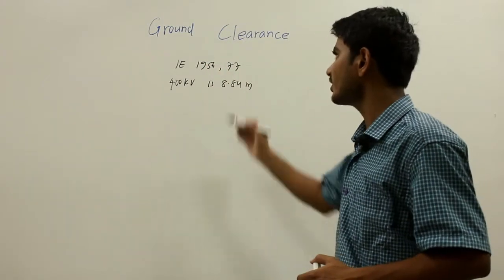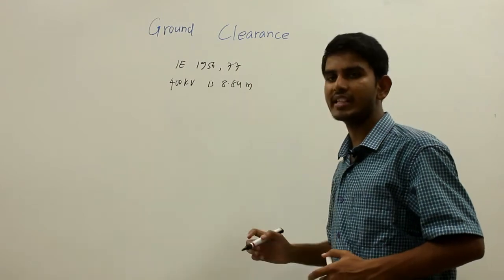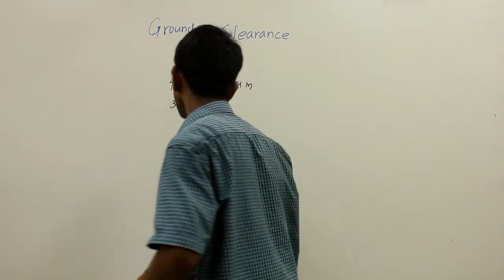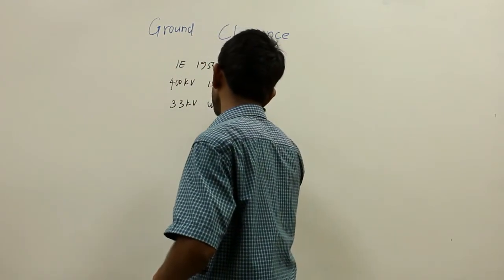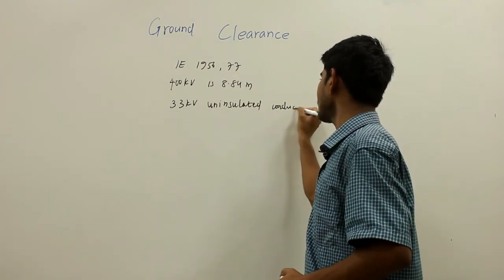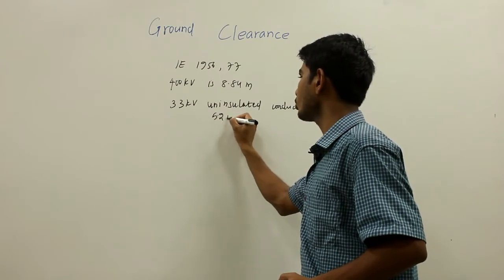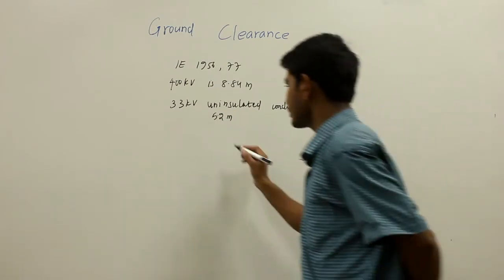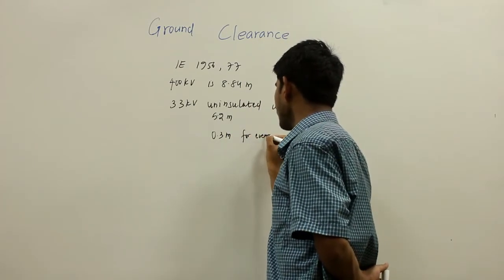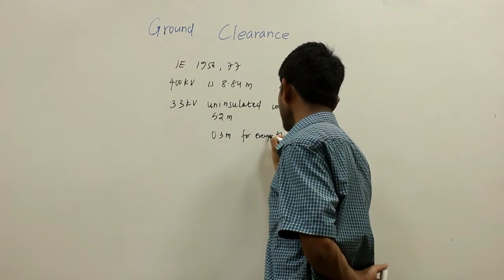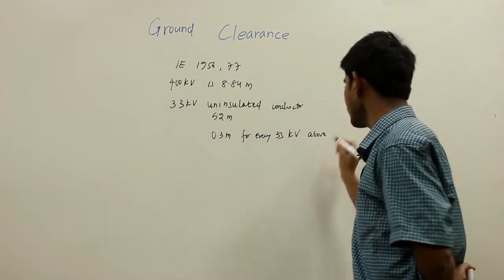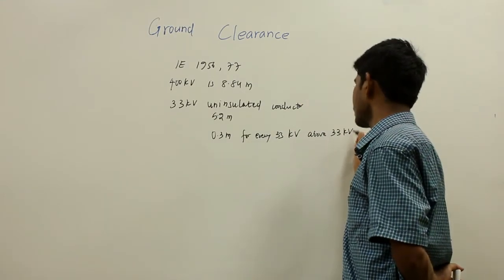Now, according to the same Indian Electricity Rules of 1956, Clause 77, the minimum ground clearance of a 33 kV uninsulated electrical conductor is 5.2 meters. And this clearance is increased by 0.3 meters for every 33 kV above 33 kV, we are going to increase the clearance by 0.3 meters.